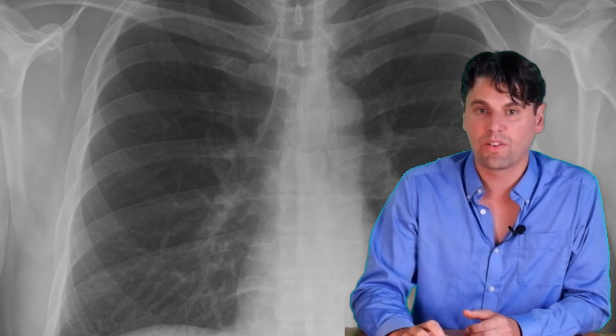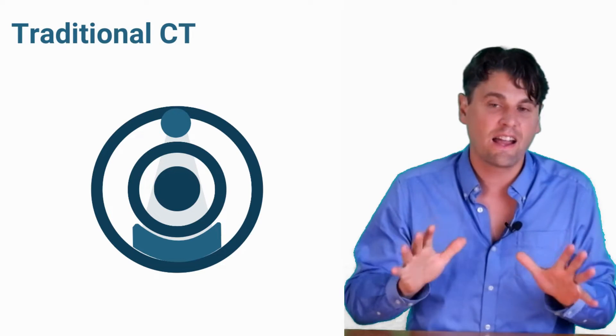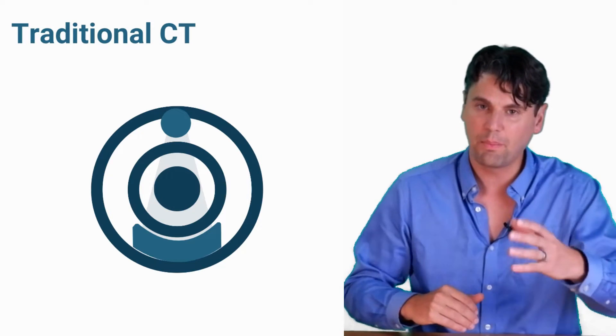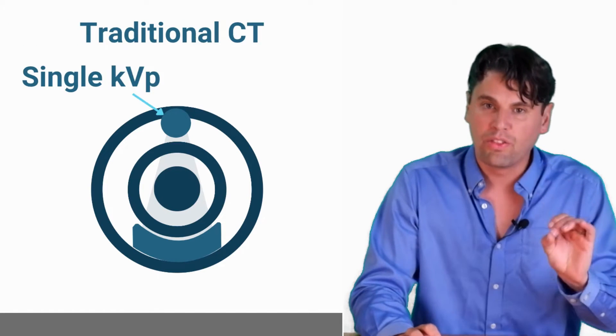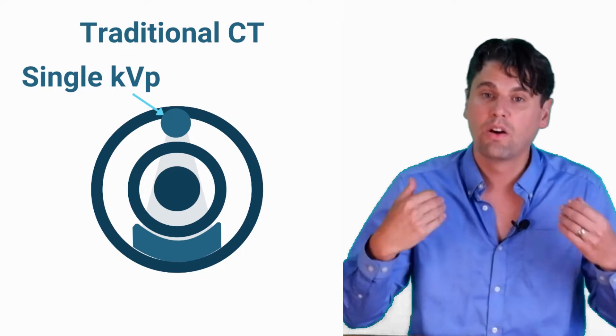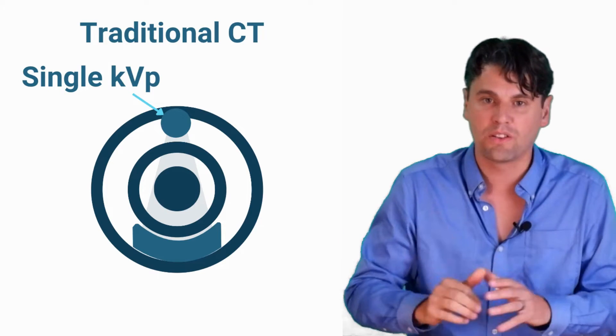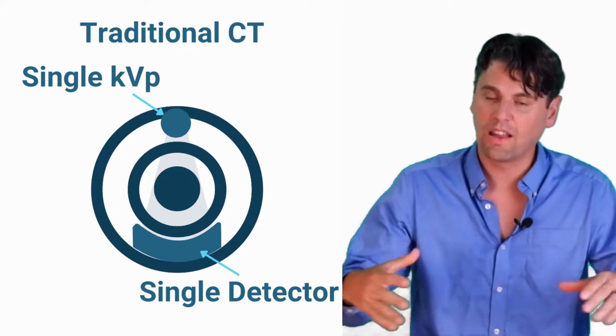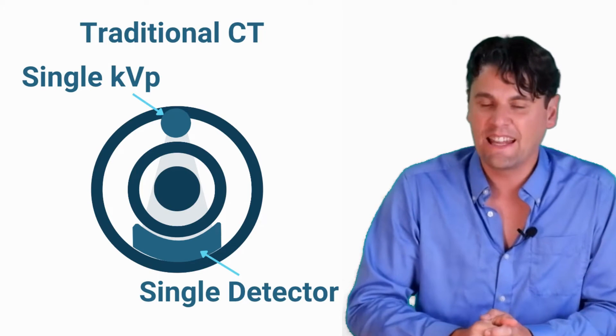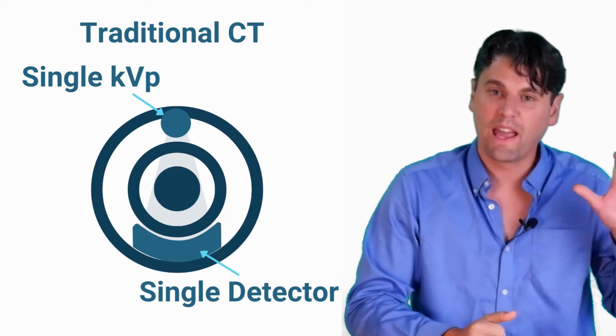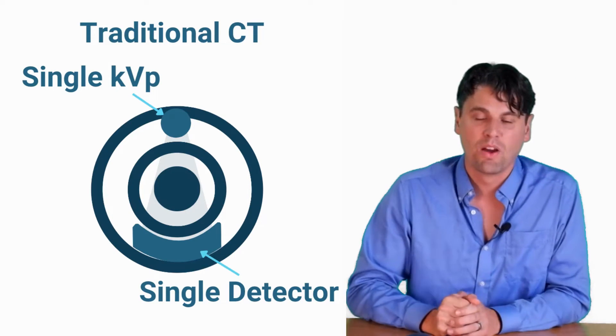Dual energy CT was a twinkle in Hounsfield's eyes even back in 1973. The idea is that you could get more information than just a standard CT image if you can actually change the color within the acquisition or the detection from your CT system. Our CT system is composed of an x-ray source and an x-ray detector. The x-rays travel through the patient and the contrast is generated by the difference between those x-rays that stop in the patient and the x-rays which travel through the patient. Traditionally, we have one single KVP for our x-ray tube used throughout the whole acquisition, measured at a single detector integrating all the energies incident on it.